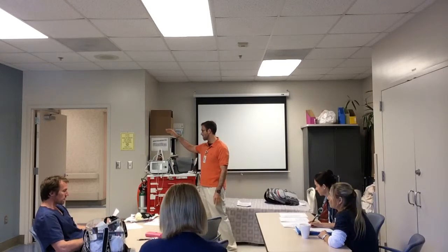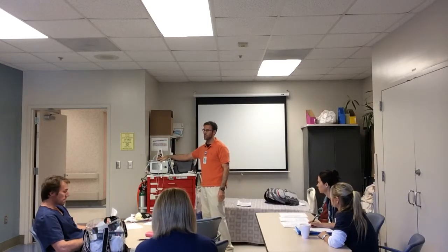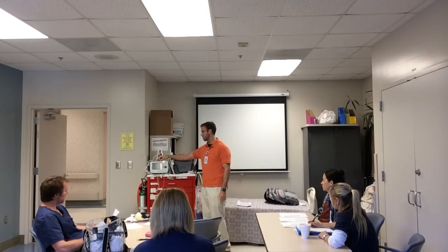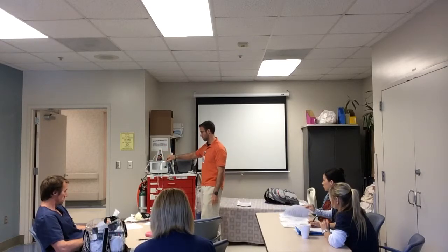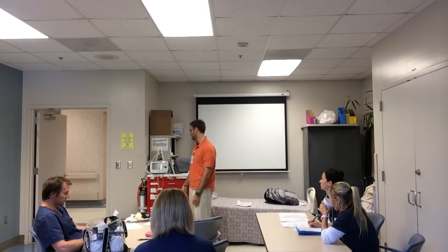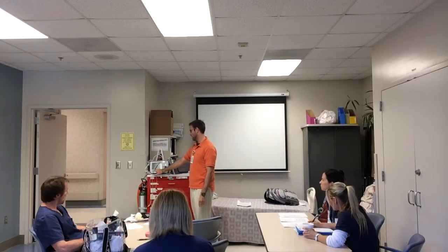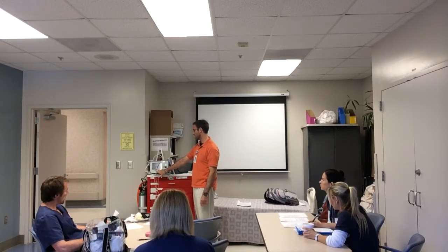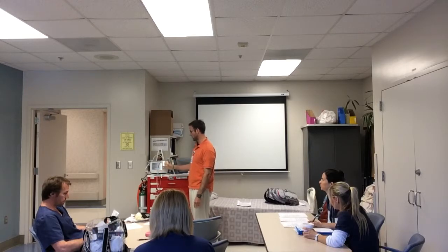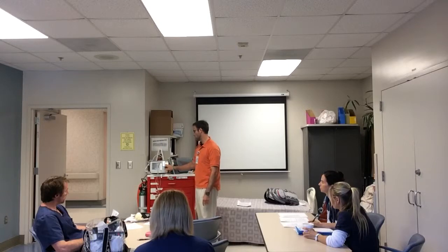We've also changed, instead of having your standard airport AED, we've upgraded to the Zoll defibrillator here. It's got your normal AED mode. You have an RRT call, you can turn it to AED mode, same setup. It'll talk to you, prompt you, just like an AED. You can also switch it over to manual mode. The button's down here, confirm it, and you get a whole bunch more buttons. You can change your leads, you can charge, analyze, synchronize, all those good things.